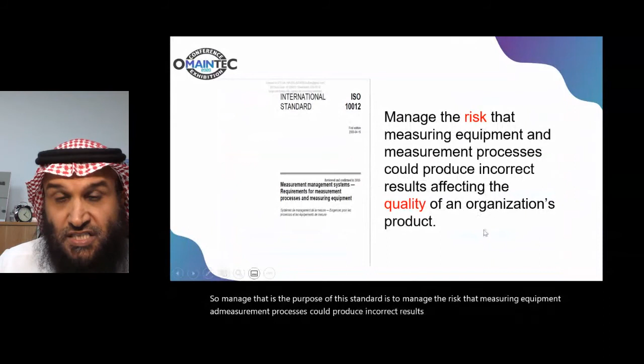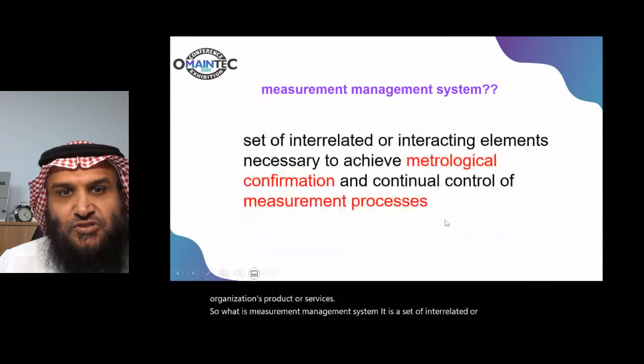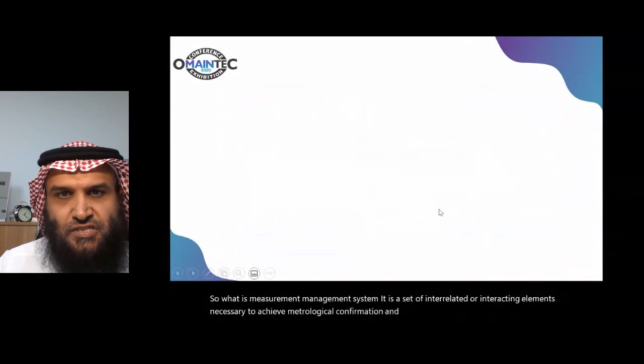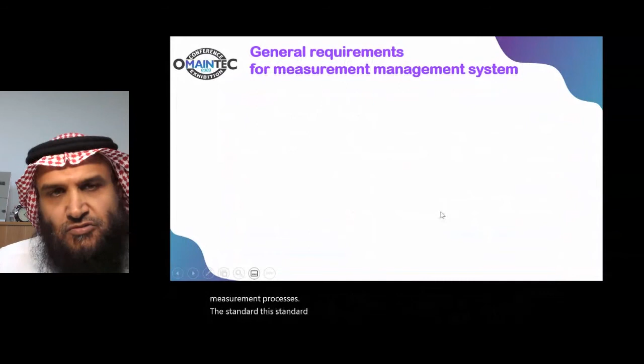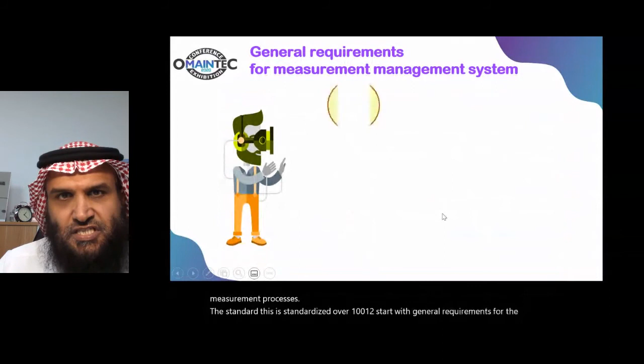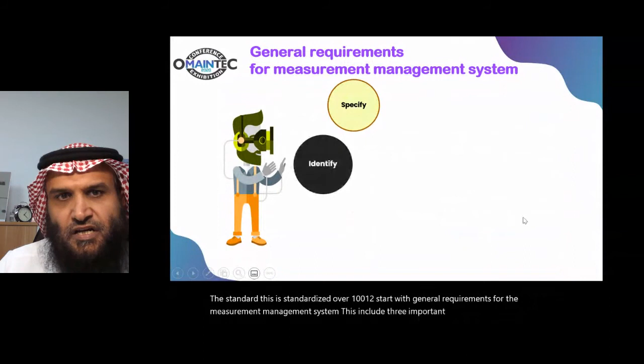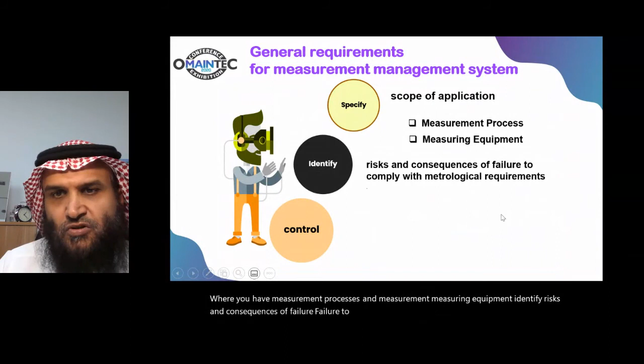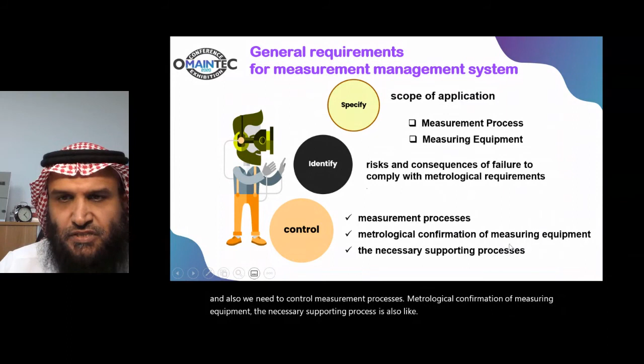So what is a measurement management system? It is a set of interrelated or interacting elements necessary to achieve metrological confirmation and continual control of measurement processes. The standard, this standard, ISO 10012, starts with general requirements for the measurement management system. This includes 3 important actions: specify, identify, and control. Specify the scope of application, where you have measurement processes and measuring equipment. Identify risks and consequences of failure to comply with the metrological requirement. And also we need to control measurement processes, metrological confirmation of measuring equipment, and the necessary supporting processes also, for example, the delivery, shipment, and handling of the measurement equipment.